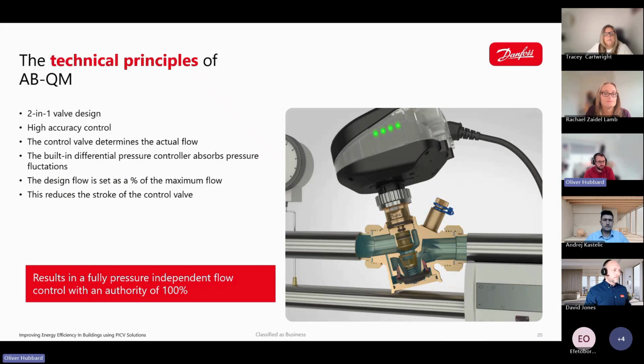So the ABQM essentially is a 2-in-1 valve design combining a control valve and an automatic balancing valve into a single body, which makes it different from a traditional control valve setup. It doesn't rely on any external balancing devices or system conditions to behave correctly. It manages all of it internally. At the heart of the valve is the control section, which determines the actual flow through the unit. Behind that, in the valve body, is a differential pressure controller. The job of this is to absorb and compensate for any pressure fluctuations in the system.